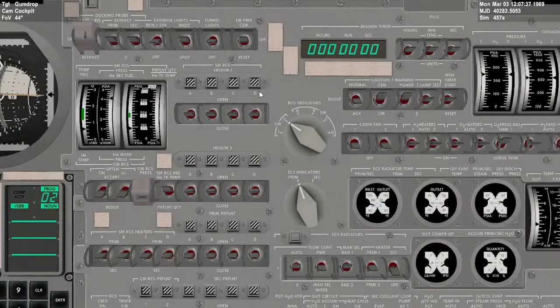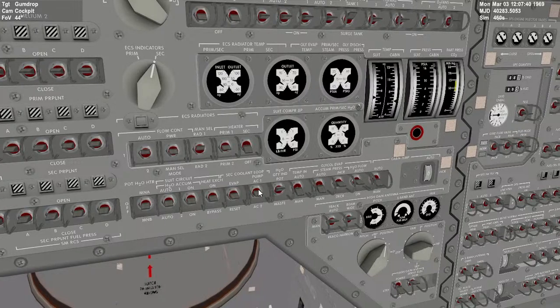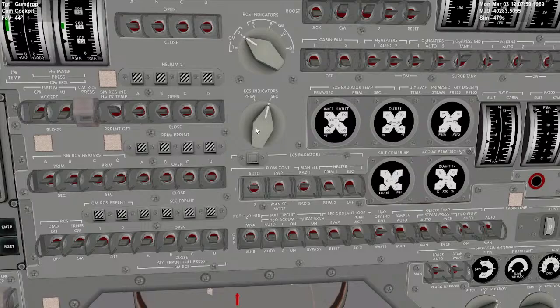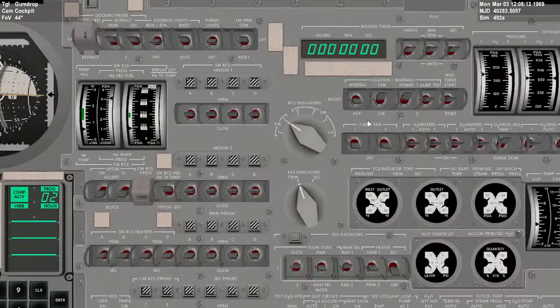Glycol to radiator flow secondary. Sorry, not evaporator. Select secondary. Take a pump 1 to AC1. Or secondary pump to AC1, and the accumulator has fallen. Good. Test AC2. Holds discharge pressure. Good. And set off. And the pump spools down. Good. Set primary. Flow bypass. Good.